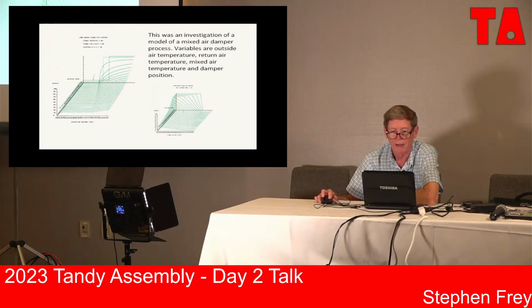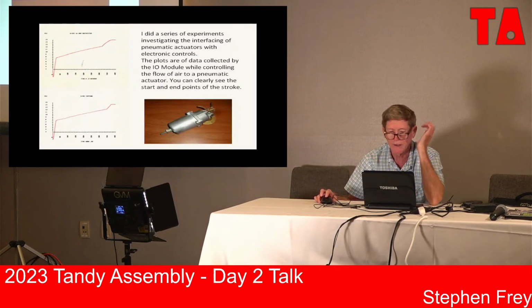So there you go. Some of the graphics I did involved a lot of surface plotting related to modeling of systems. These relate to mixed air damper processes - how the mixed air mixes with outside air and return air, and the mixed air, return air, and damper position, and what effects these all have. I could see what the process gains are and everything else.